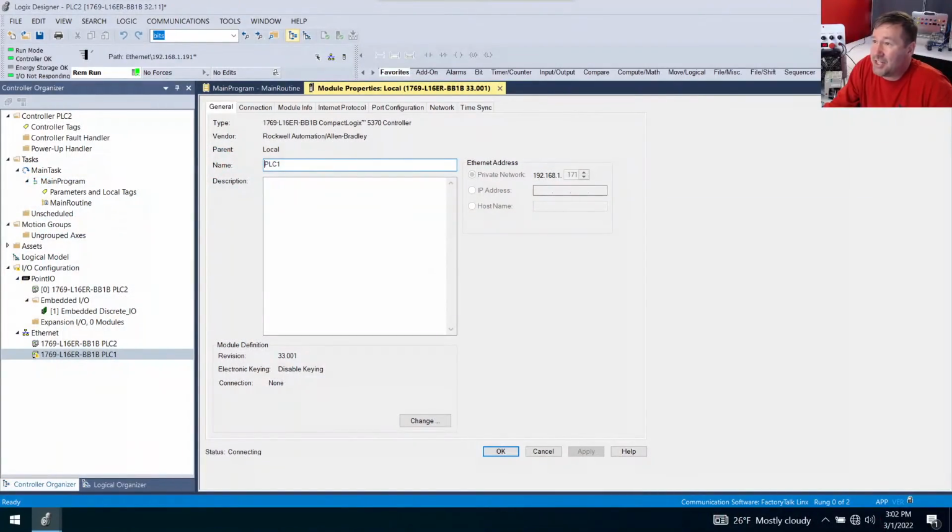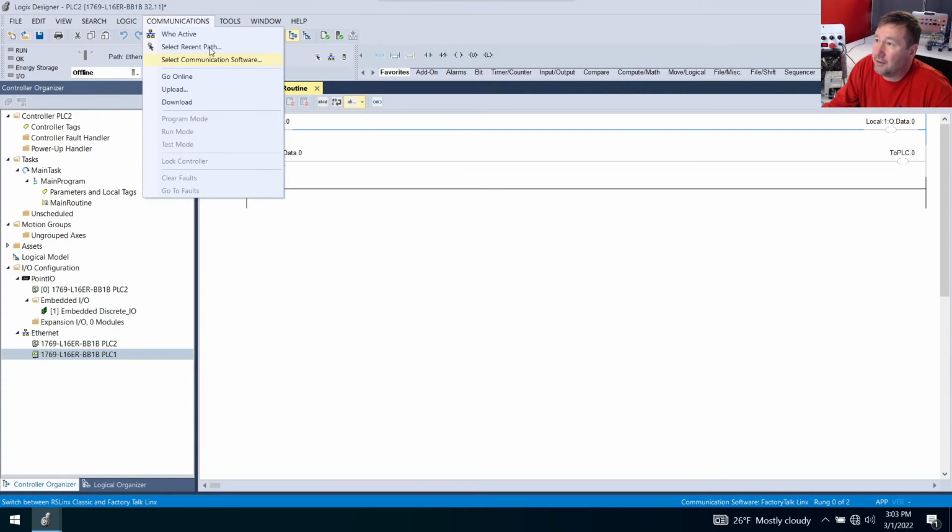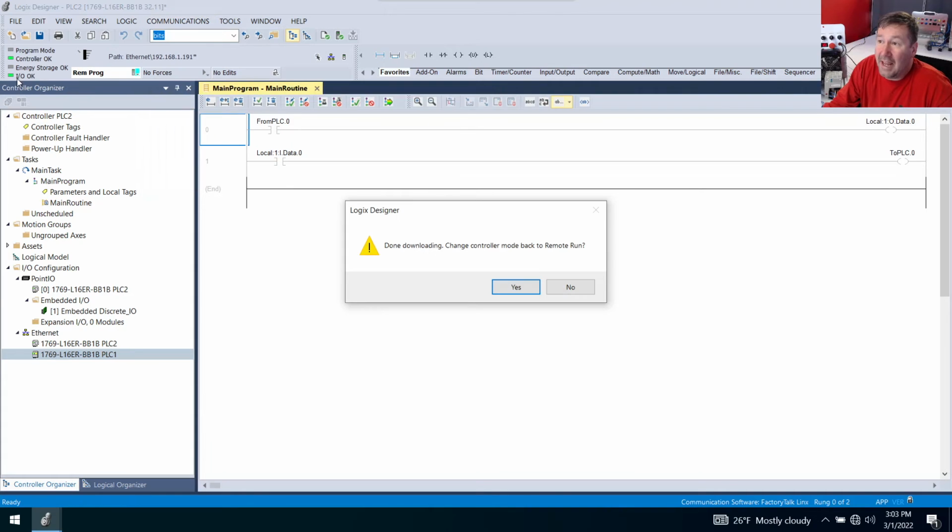So you cannot change this online. We are going to have to go offline. And then I can change this to 181, and I'll be able to re-download that and hopefully fix this problem. Now this is what it should look like. I/O okay, solid green, looking good.